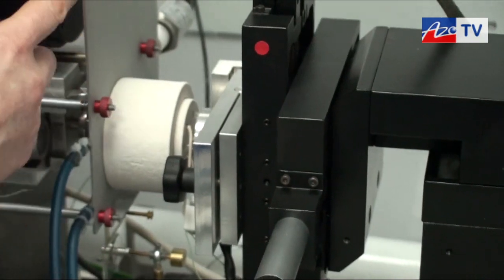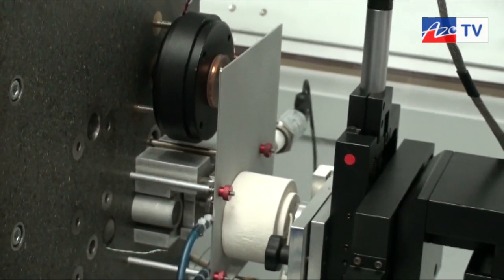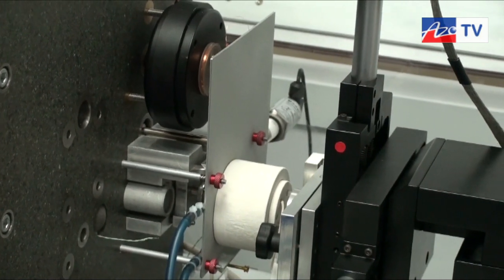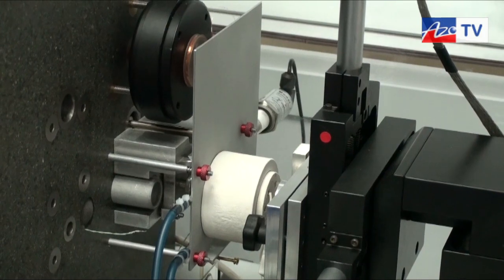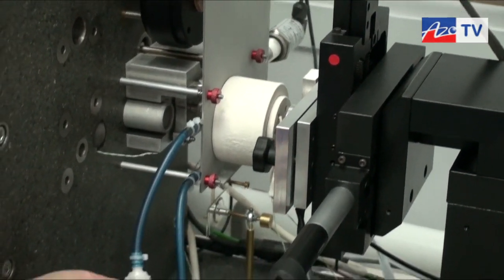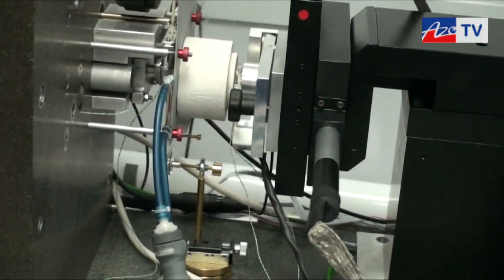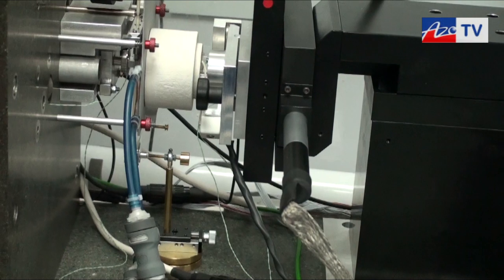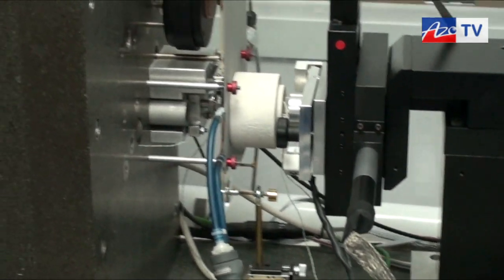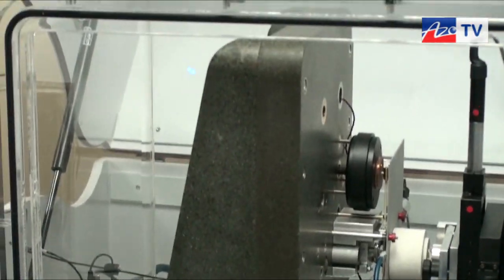So on the left then we have, this is a little heat shield, which just is extra kind of insurance against any heat effects on the loading train. And because this instrument works up to 750 degrees, we water cool that heat shield. The instruments that only go to 500 degrees, you don't need the water cooling, it's just the shield to block any radiation off the sample onto the loading head. So it's a very simple setup, but very, very effective. What we do is we heat the indenter, we heat the sample.